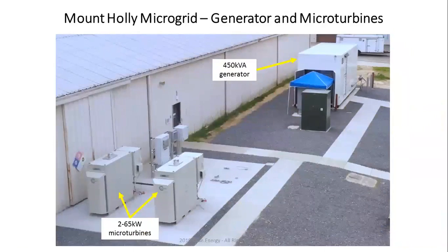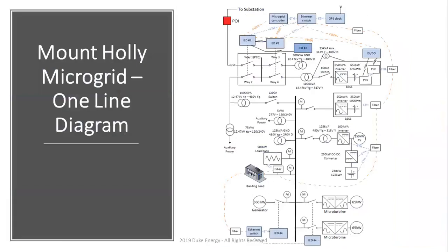So as you can see, we have 5 distributed energy resources over here. Natural gas generator, micro turbines, which is inverter-based, AC coupled battery, which is inverter-based, PV system, and DC coupled battery. So that's pretty much what we have inside the yard.